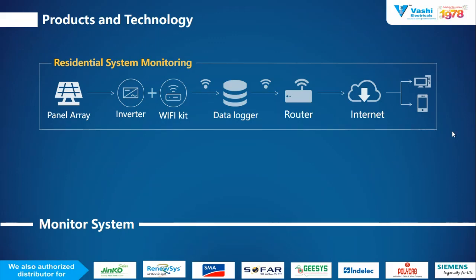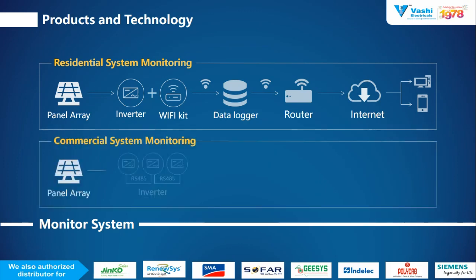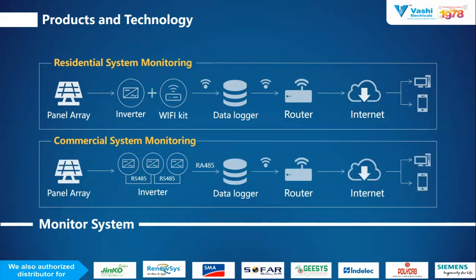The second system is commercial remote monitoring, in which a number of inverters are connected in series by RS485 communication. Manoj, next, if you press click, then you can easily check the commercial system monitoring. Yes. So in this commercial remote monitoring, a number of inverters are connected in series by RS485 communication. By this Modbus communication, the data logger can generate the data and send it over the cloud, so the user can easily monitor the data on the mobile as well as the web browser.